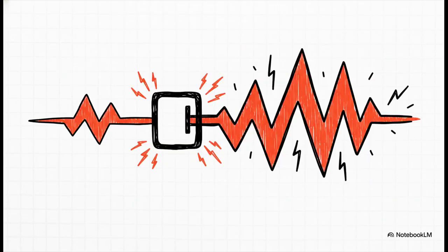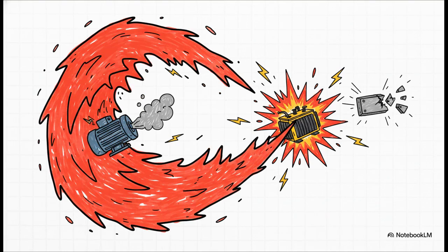And that monster has a name: resonance. This is the stuff of nightmares for electrical engineers. It's what happens when your filter, the thing that was supposed to be the solution, accidentally tunes the entire building's wiring to the exact same frequency as the harmonic noise it's trying to eliminate. And when resonance happens, the filter becomes an amplifier—instead of removing the harmonics, it magnifies them hugely.